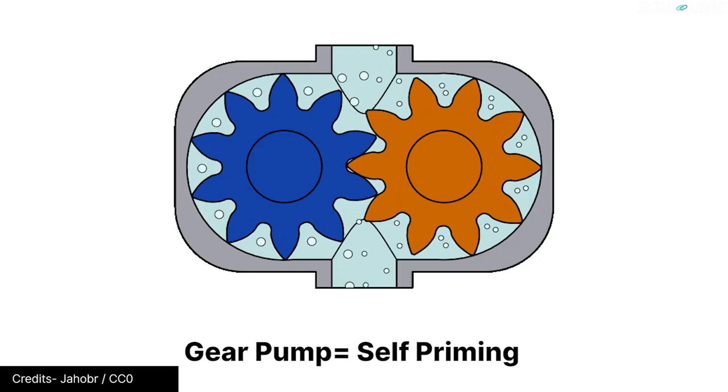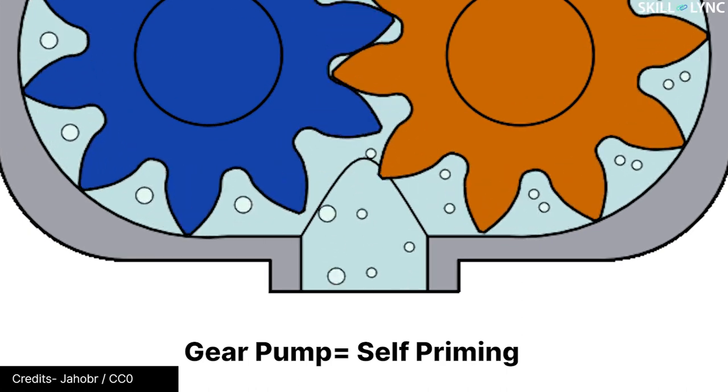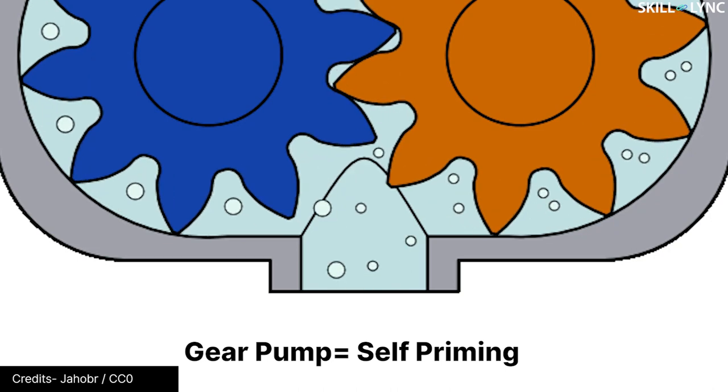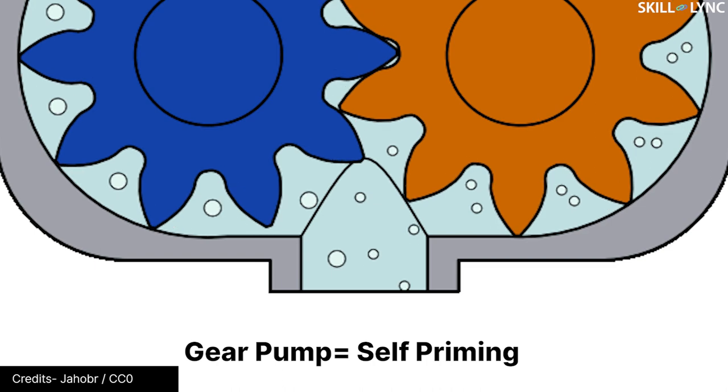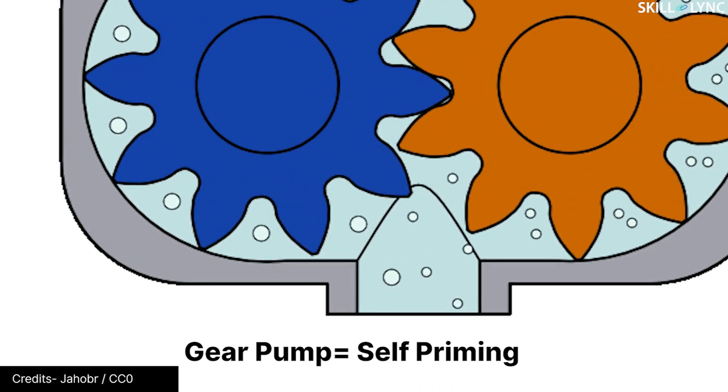As the gears of the pump rotate, they get separated at the suction side of the pump. This area is generally filled with fluid. Even if the suction area is not filled, the gear pumps are self-priming. This means they are capable of generating sufficient suction pressure to pull the fluid towards the gears for pumping. This is the end of the suction operation.